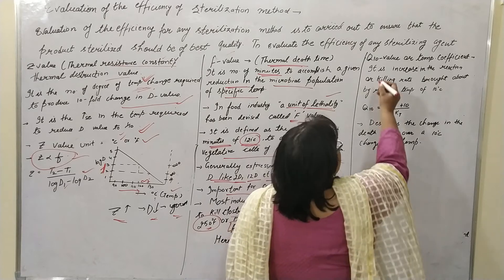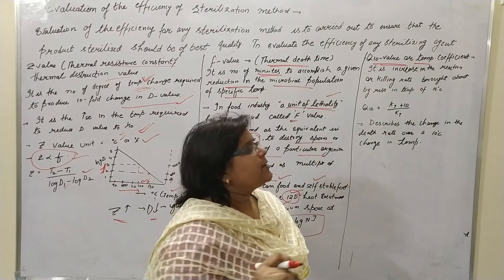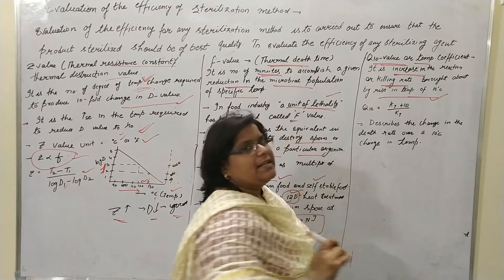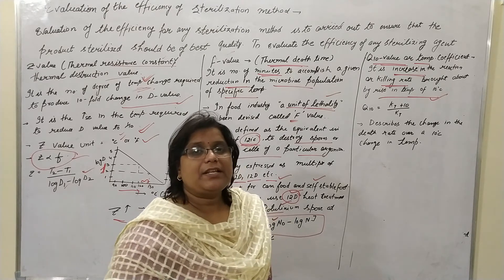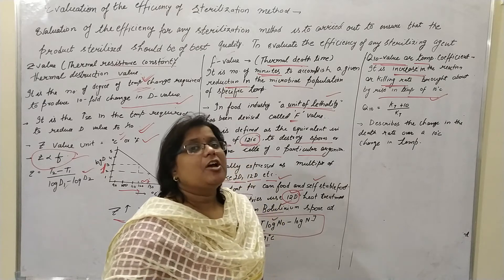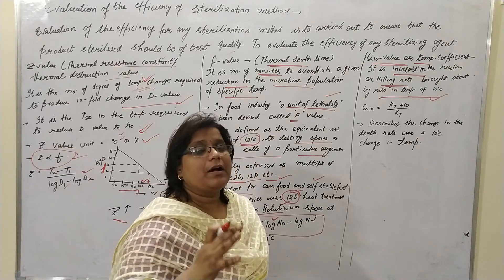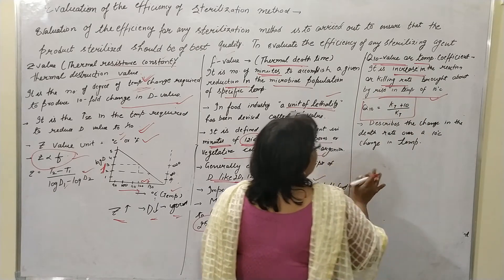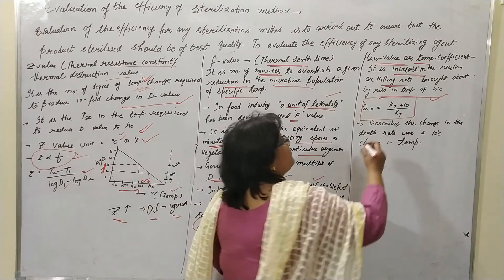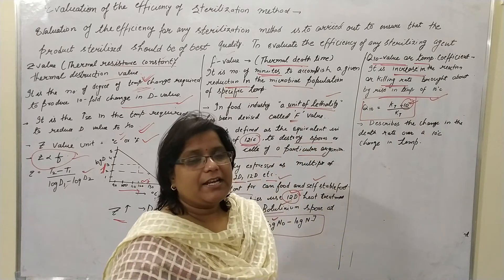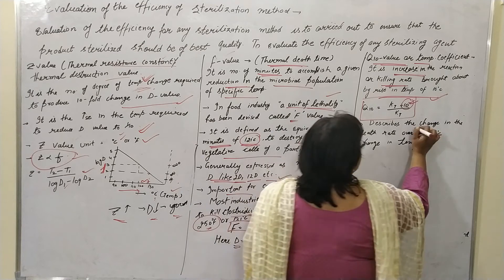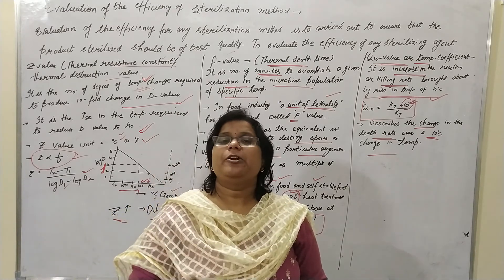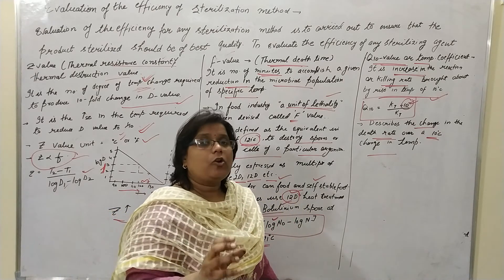Now the second-to-last parameter is the Q10 value or the temperature coefficient. The Q10 represents the increase in the reaction or killing rate by increasing the temperature by 10 degrees Celsius. It means, if we increase the temperature by 10 degrees Celsius, how much efficiency of the sterilizing agent is increased or enhanced. The Q10 is represented by k(t+10) divided by k(t), where k(t) is the rate at temperature t and k(t+10) is the rate at 10 degrees higher. It describes the change in the death rate over a 10 degree Celsius change in temperature.